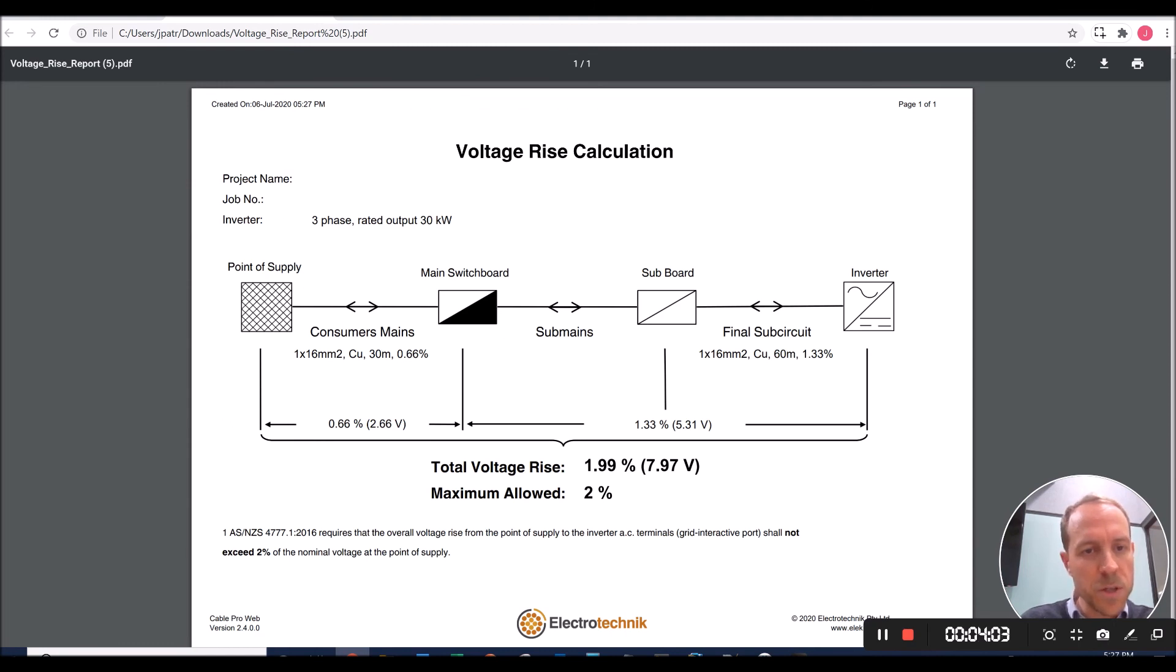Then we've got the consumer's mains. Again, we have a one circuit of 16 square millimeter copper conductor over 30 meters. Our voltage rise is 0.66%. Total voltage rise for the installation is 1.99% or 7.97 volts, which meets our requirement of a maximum voltage rise of 2%. There we have it. We have a nice complete report, which we can submit to our power authority for approval.